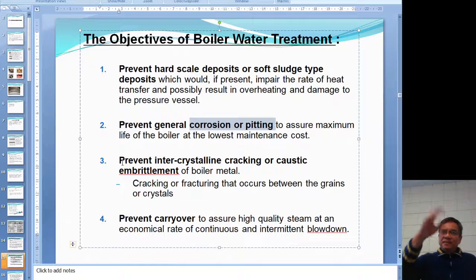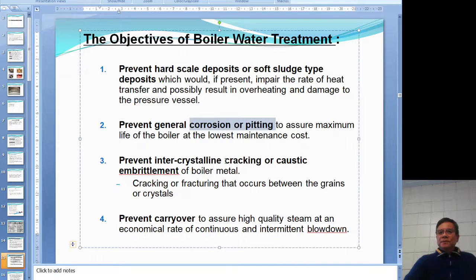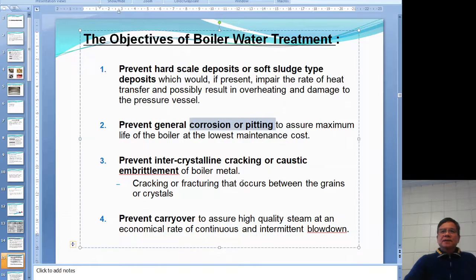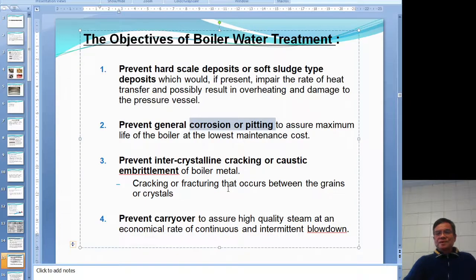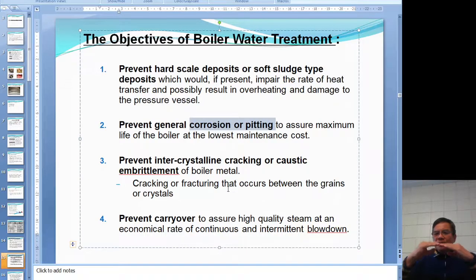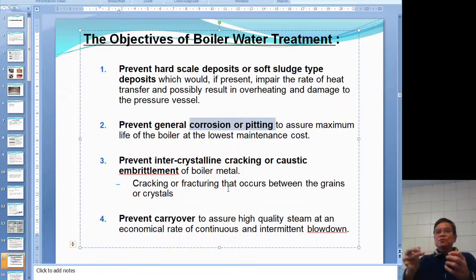A third objective — closely related to corrosion — is to prevent intercrystalline cracking, also called stress corrosion cracking or caustic embrittlement. Cracking or fracture occurs between the grains of the crystal structure of the boiler metal. A small corrosion site can start a crack between two grains, and as corrosion continues, the stress corrosion crack propagates until the material fails.